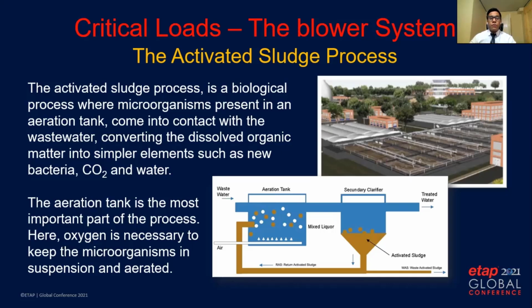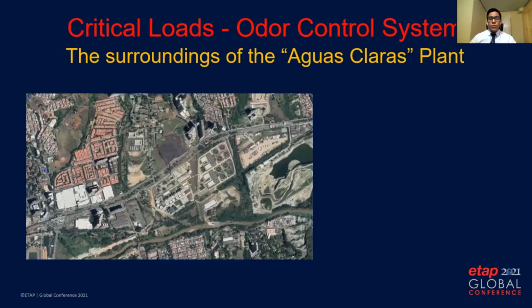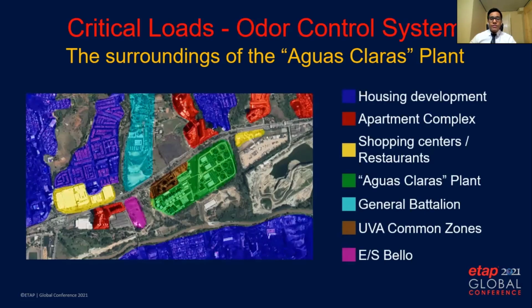For this reason, the blowing system is a critical load that we must keep in line at all times. Other critical loads are the odor control system that prevents odors in the preliminary and primary treatment. Let's now see the importance of proper odor control in the plant. On this map, we find the area surrounding the Aguas Claras wastewater treatment plant. As you can see, most of the buildings around are urbanizations and shopping centers, where the comfort and health of the inhabitants of the area is important. On the other hand, the UVA Aguas Claras is one of the 14 articulated life units of EPM, a place to learn, to play, a space where homage is paid to nature and the families have the opportunity to share free time and enjoy cultural events. For this reason, the plant cannot produce bad odors that pollute the air in the area.